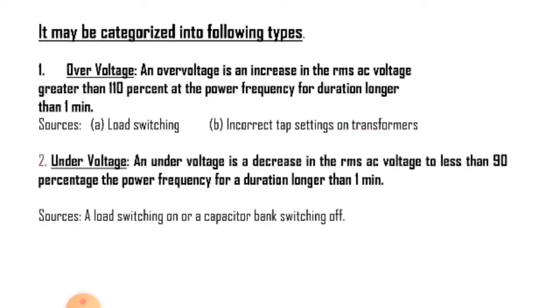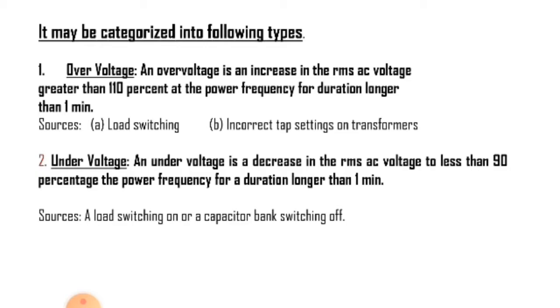Regarding under voltages, it is defined as a decrease in the RMS AC voltage to less than 90 percent at the power frequency for a duration longer than one minute. Under voltages are the result of switching events that are the opposite of the events that cause over voltages. A load switching on or a capacitor bank switching off can cause an under voltage until voltage regulation equipment on the system can bring the voltage back to within tolerance. Overloaded circuits can also result in under voltages.